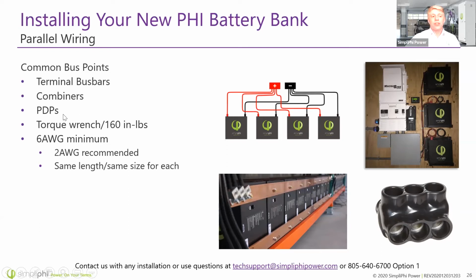Another option for combiners is to use power distribution panels. These are available with almost every inverter that you buy. They will offer you a PDP or maybe a mini PDP. Both are going to be great and can serve as your connection point for your batteries. Make sure to use 6 gauge minimum wire size, but often we see 2 gauge used most often. It depends on the length of the run what wire size you actually need, but I usually just recommend 2 gauge from each battery to the connection point to be safe.